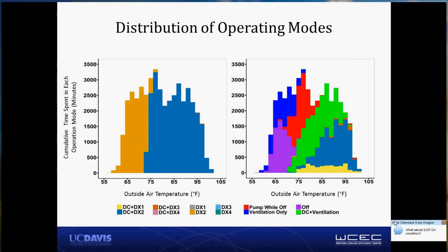You can see it changing over there at about 70 degrees with fair consistency. That system runs in DX2 all the time, 24 hours a day. It never turns off. The unit on the right has a much broader diversity of operating modes. You can see for a significant portion of time it's running with the dual cool only while the system is running in ventilation. The compressors aren't even running. And then also a significant portion of time running in first and second stages.